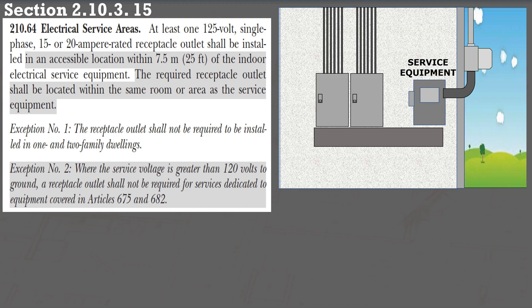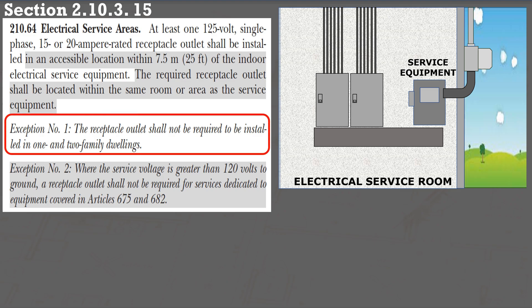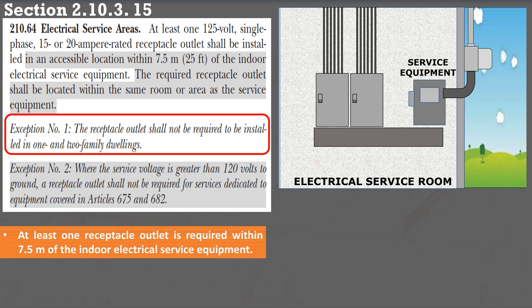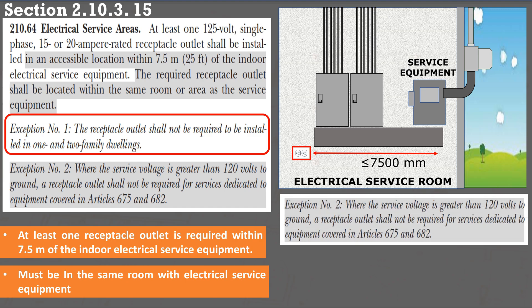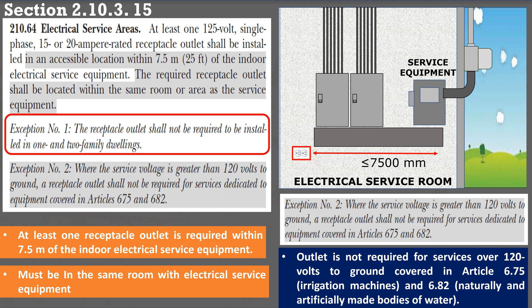Section 2.10.3.15 covers the electrical service area for multi-family dwelling units, as mentioned in exception number 1. For the indoor service area, at least one outlet is required in an accessible location within 7,500 mm from the indoor electrical service equipment, and this outlet must be in the same room as the service equipment. Exceptions also apply if the service voltage is over 120 volts to ground, and for services dedicated to equipment covered in article 6.75 (irrigation machines) and 6.82 (naturally and artificially made bodies of water), as stated in exception 2.